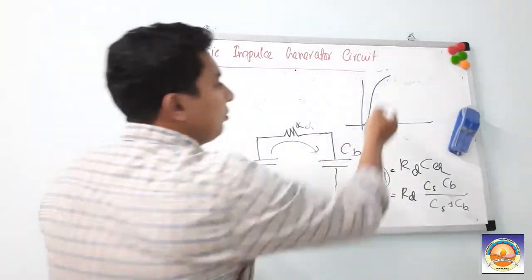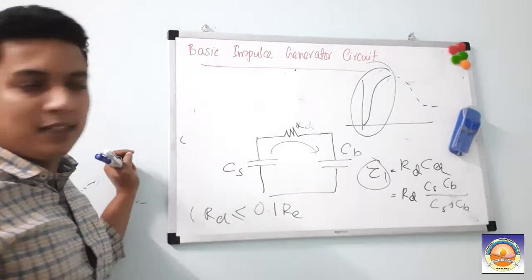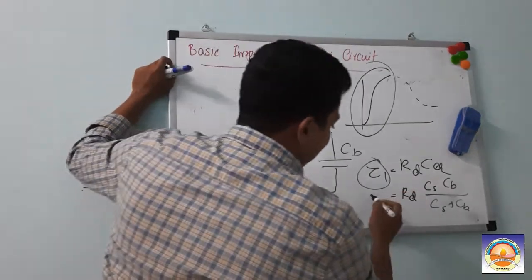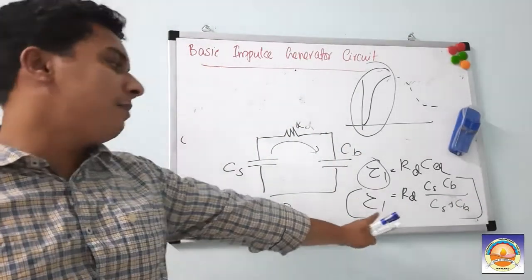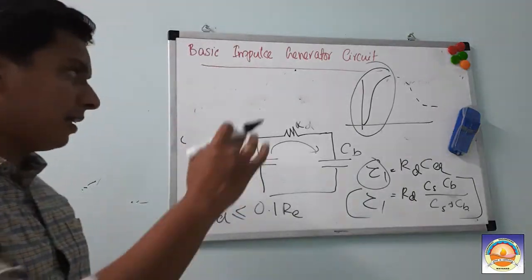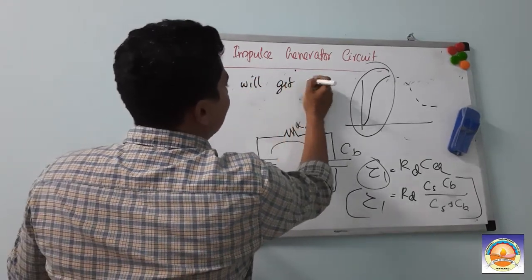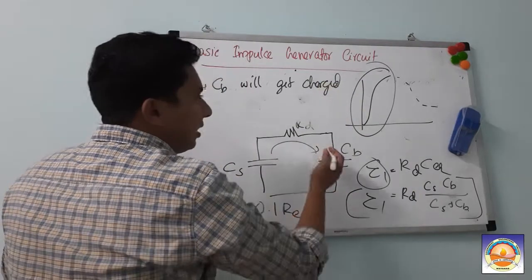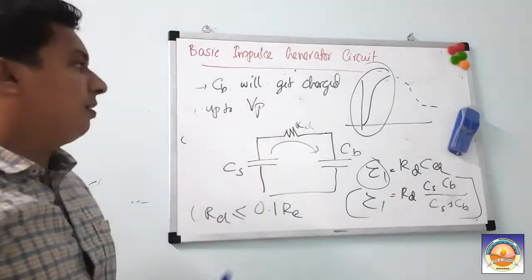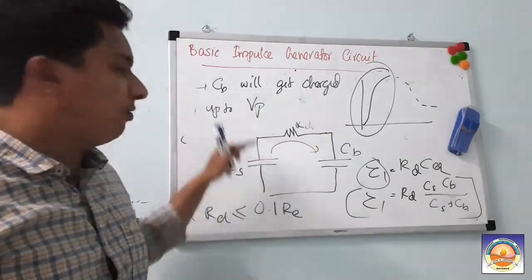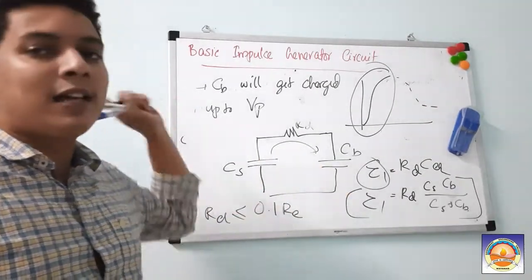In the impulse voltage waveform, this charging process creates the first initial rising part of the wave. Your CB gets charged up to a maximum voltage Vp — the peak value. Once the peak value is achieved, afterwards both CS and CB will get discharged through your RE.